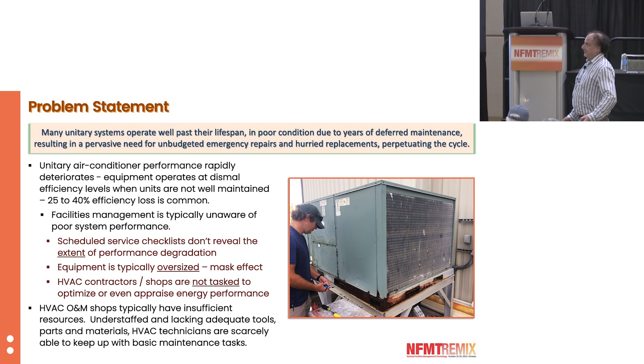So in addition to the condenser coil corrosion and low charge, here's a bunch of other things. Refrigerant charge, valve, coil, a failed or slow condenser fan motor. That's a common thing when maybe a unit has 2 or 3 fan motors and just one of them isn't working, or maybe it's turning, but it's turning very slowly. The unit can still function like that, but it's going to be much less efficient.